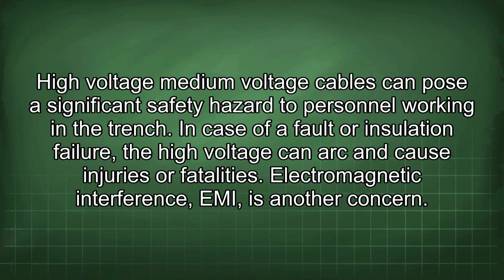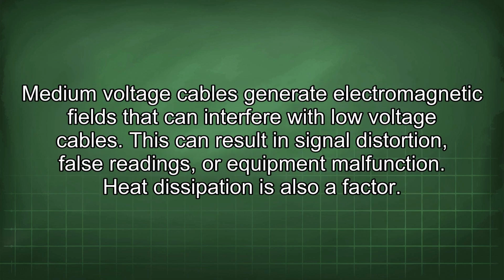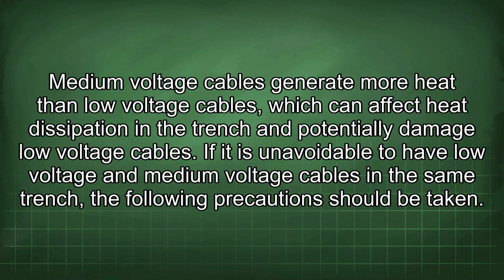Electromagnetic interference, EMI, is another concern. Medium voltage cables generate electromagnetic fields that can interfere with low voltage cables. This can result in signal distortion, false readings, or equipment malfunction. Heat dissipation is also a factor. Medium voltage cables generate more heat than low voltage cables, which can affect heat dissipation in the trench and potentially damage low voltage cables.